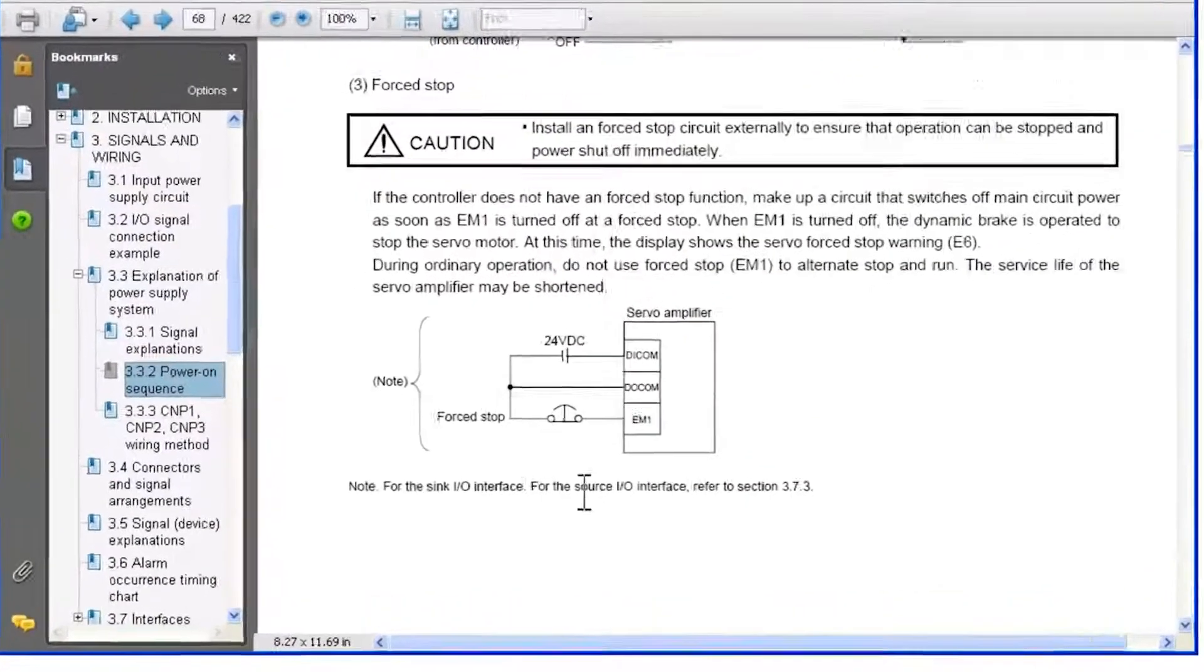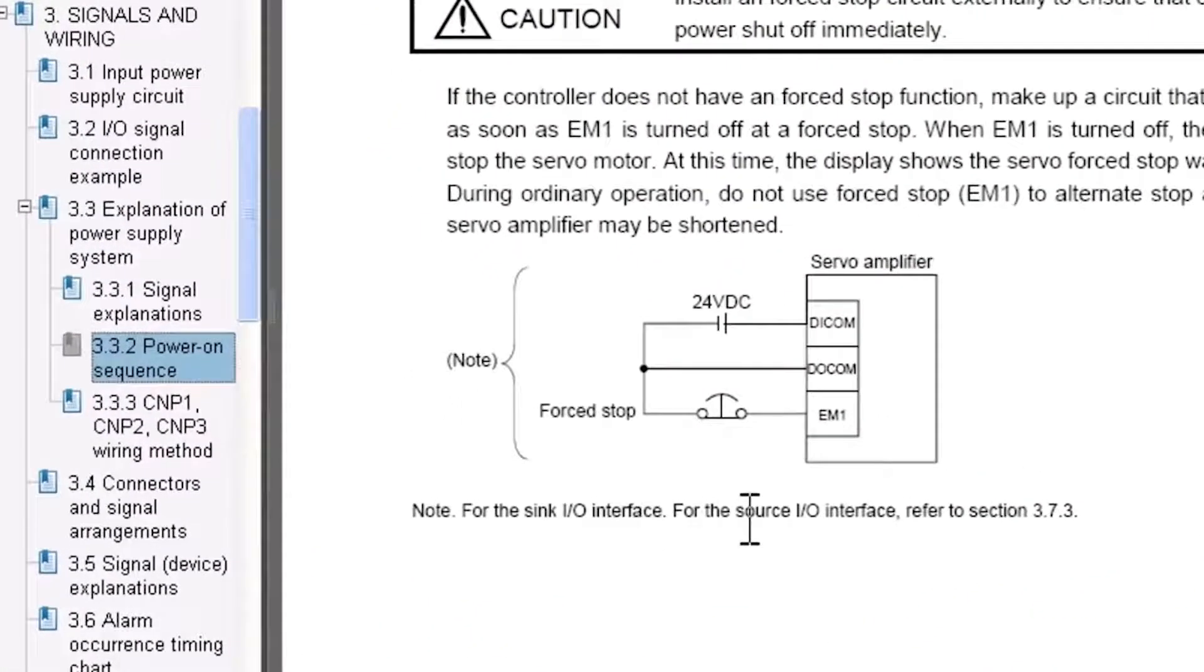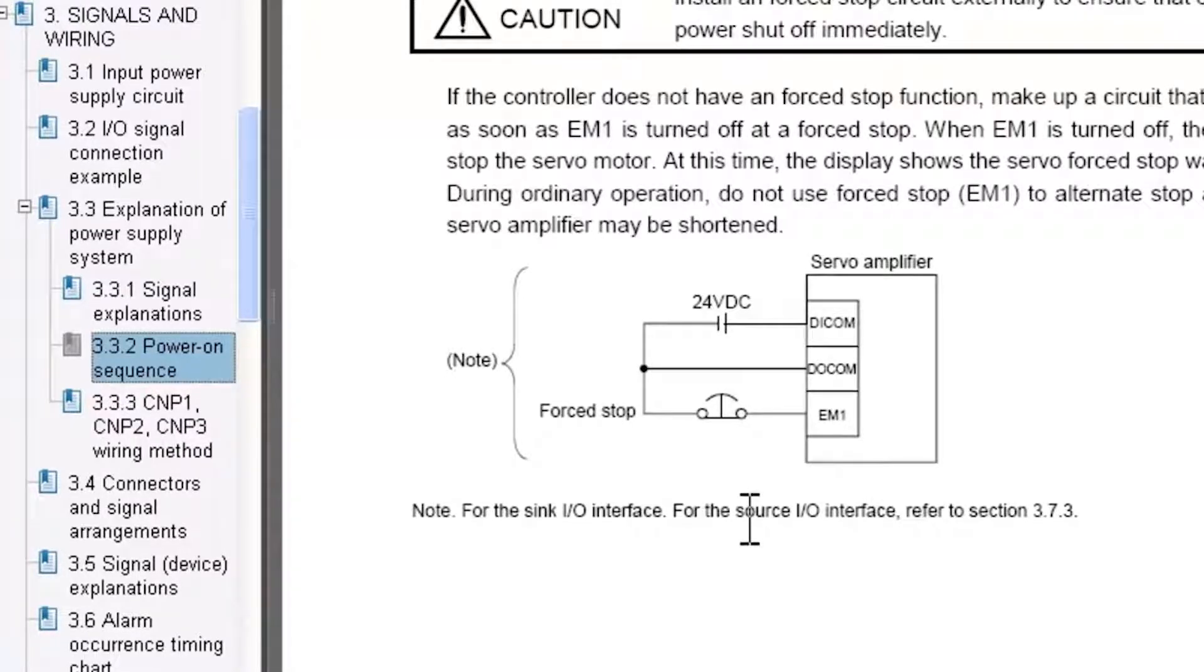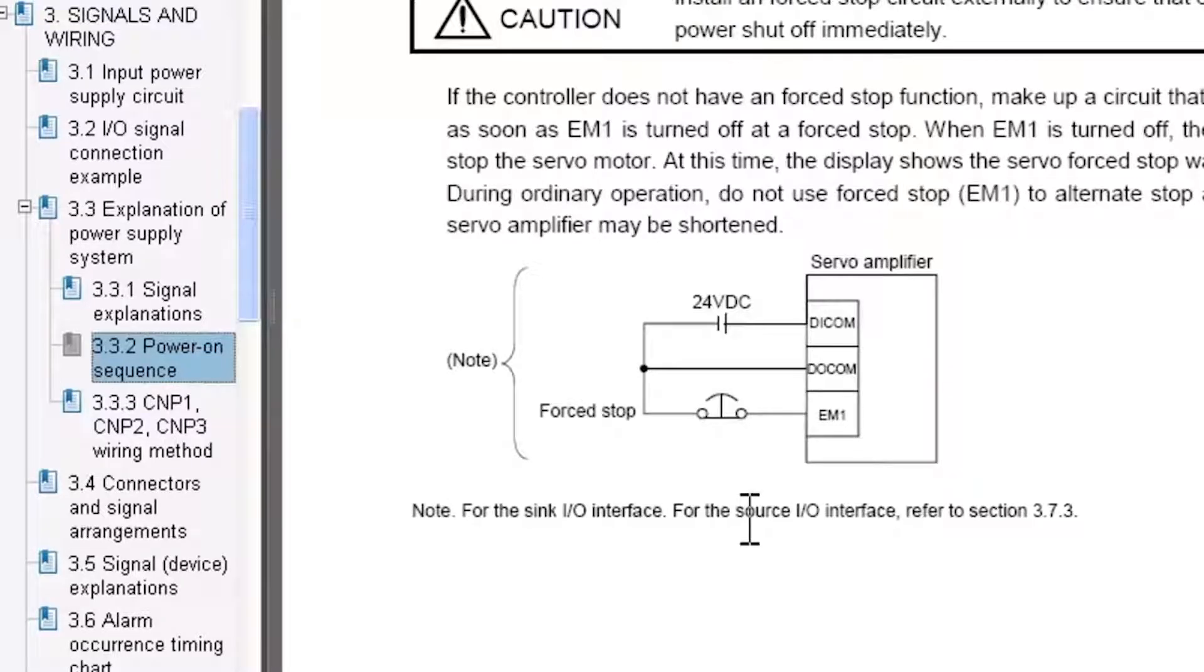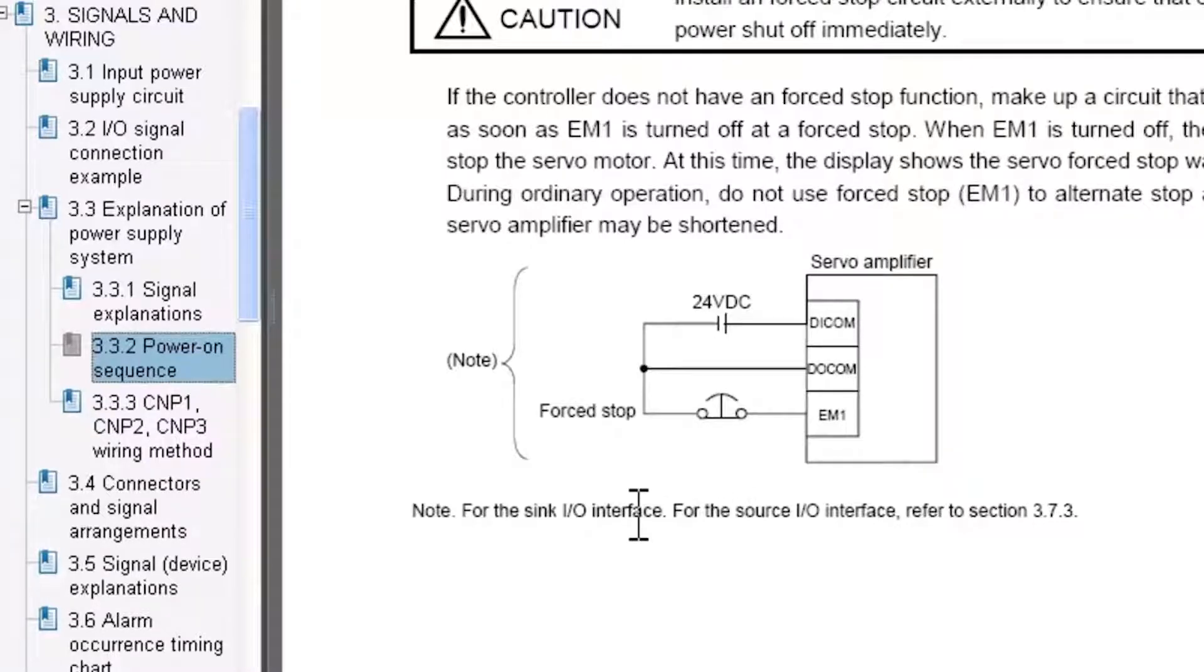Essentially what you have here is circuitry with a normally closed contact. You need to tie the negative end of 24 volts to the force stop signal into the EM1 signal on the amplifier. This diagram here highlights the wiring for a sink I/O interface.